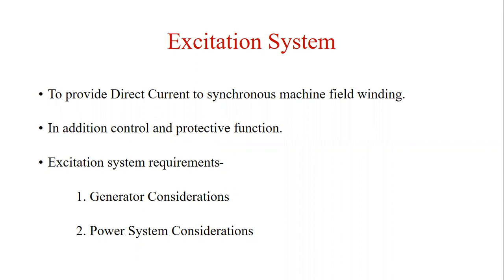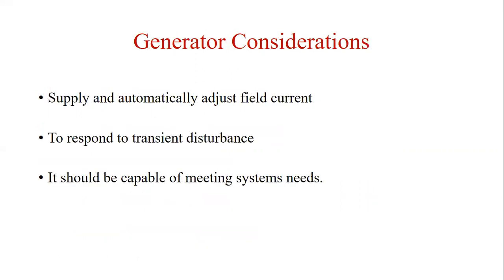Let us start with the requirements of the excitation system, which will be divided into two parts: first is the generator considerations and the other is the power system considerations. The basic requirement is that the excitation system supply and automatically adjusts the field current of the synchronous generator to maintain the terminal voltage as the output varies within the continuous capability of the generator.